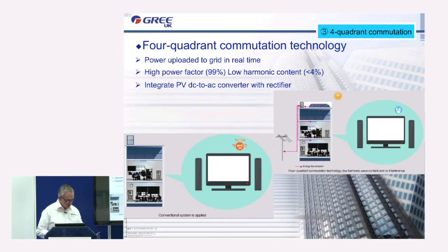4-quadrant technology, low harmonics, reduced losses, power upload in real time, integrated DC-AC converter, meaning safe, efficient PV energy control. Okay? So just trying to get across that basically with this system, the built-in control and the built-in saving in terms of the losses is a big advantage, and it means also that you don't have to add any additional components.